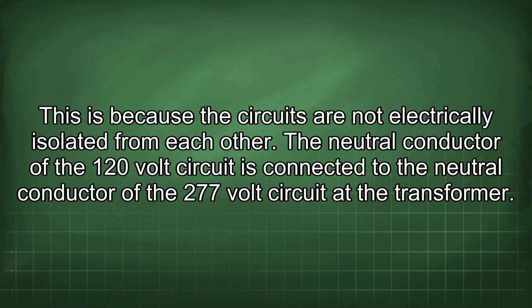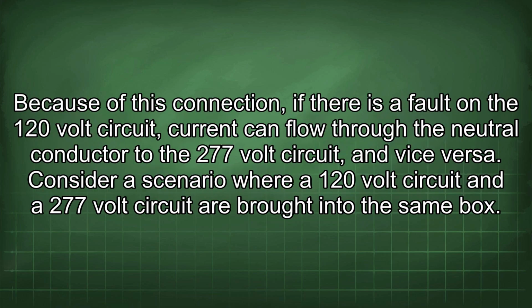The neutral conductor of the 120-volt circuit is connected to the neutral conductor of the 277-volt circuit at the transformer. Because of this connection, if there is a fault on the 120-volt circuit, current can flow through the neutral conductor to the 277-volt circuit, and vice versa.